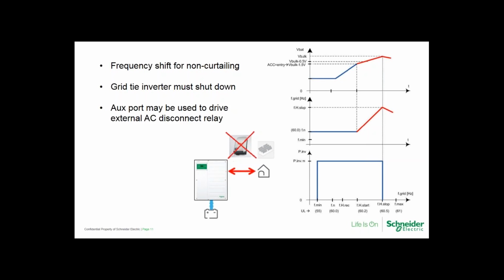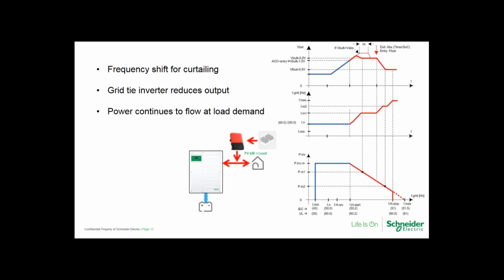And again, we're referring to using an external disconnect relay if you have an inverter that can tolerate higher frequencies, such as UL 1741SA compliant. And then, of course, SMA is the only grid tie model that I'm aware of that has what's called an off-grid mode. So they can be used off-grid with our inverter to provide a 3-stage charge if set up correctly.